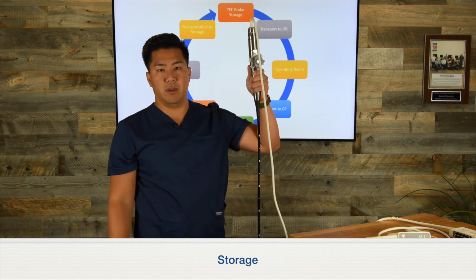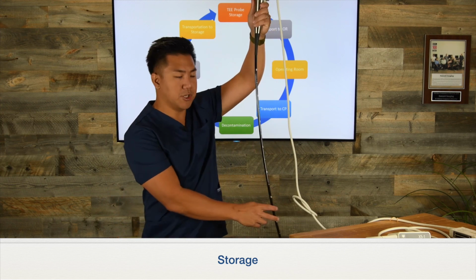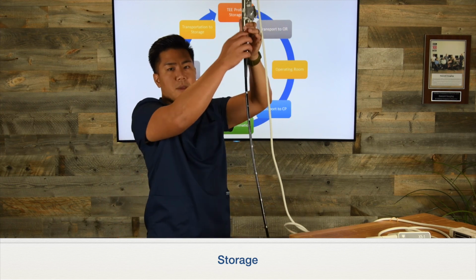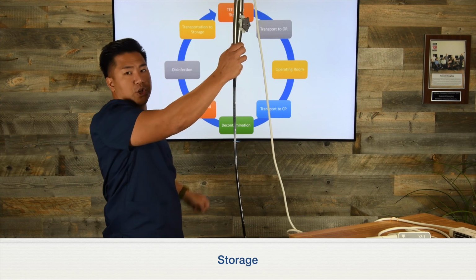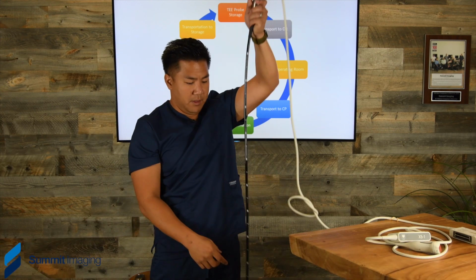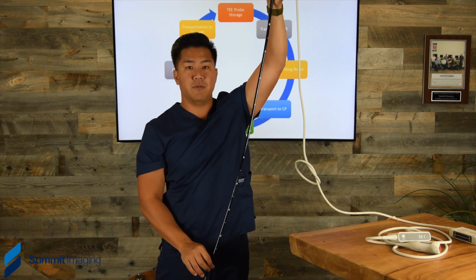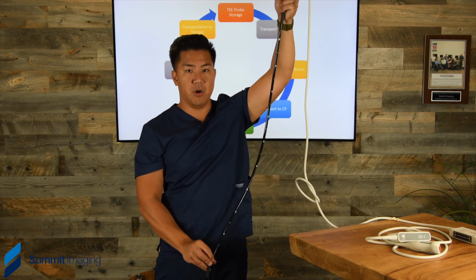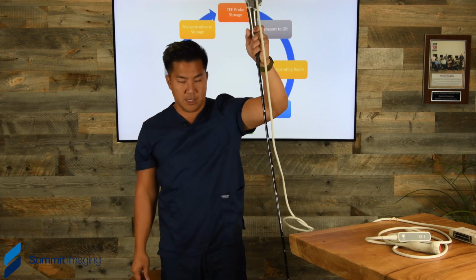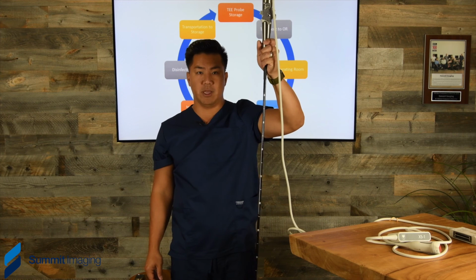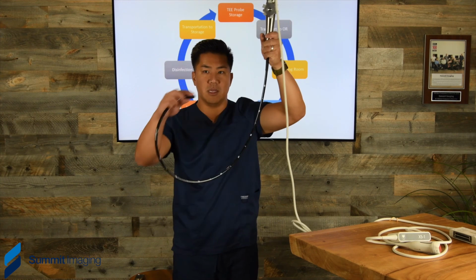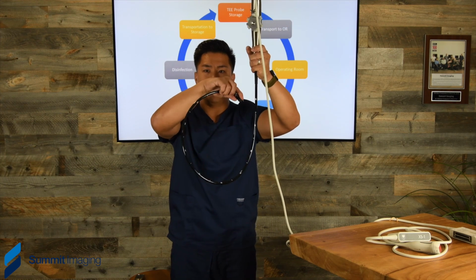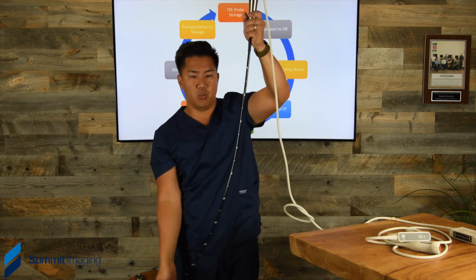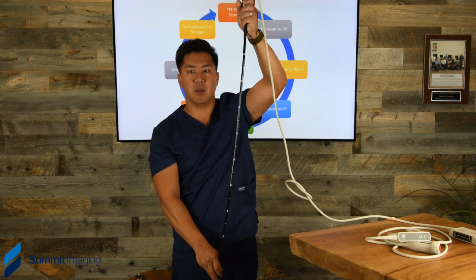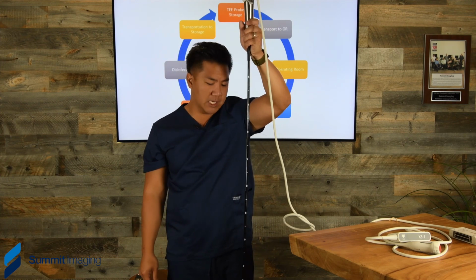But what's really important here, and what I wanted to demonstrate, is that if we skipped inspection and testing, there could be some fluid from a micropuncture in the tip of the probe. It's recommended it's stored vertically like this to prevent it from assuming a permanent coiled position. We want this to be straight so it can scan a patient as easily as possible.